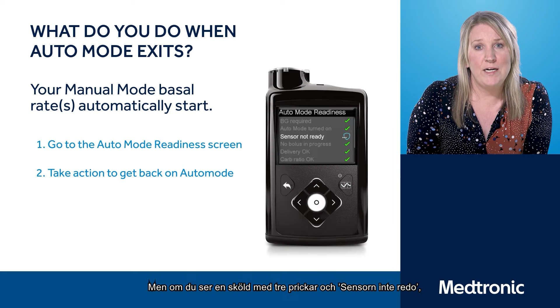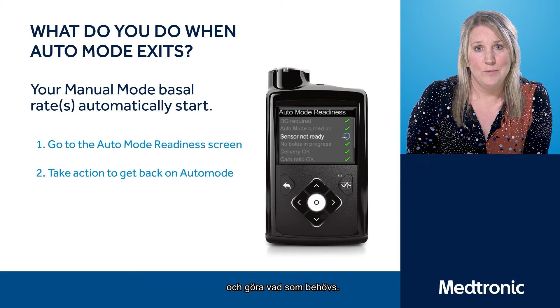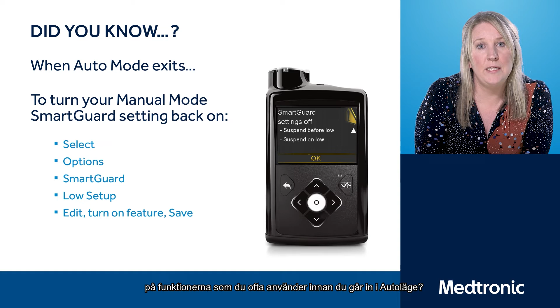However, if you see the shield with the 3 dots against sensor not ready, you simply need to sit back and wait for the sensor to update and do what it needs to do. Did you know that when auto mode exits and you're in manual mode, you need to go back into the SmartGuard settings to switch on your suspend before low, or the features that you often used prior to going into auto mode. Here on the screen are the instructions of how to do that.